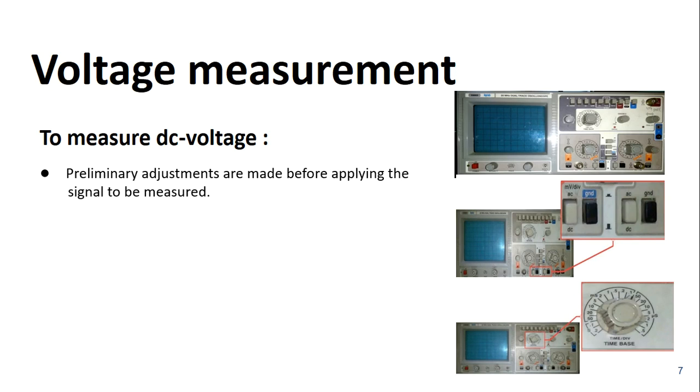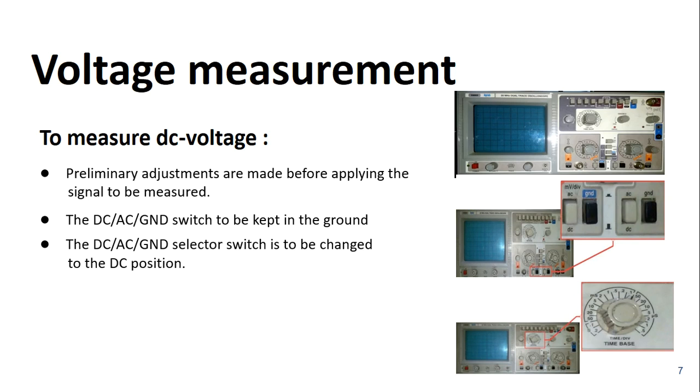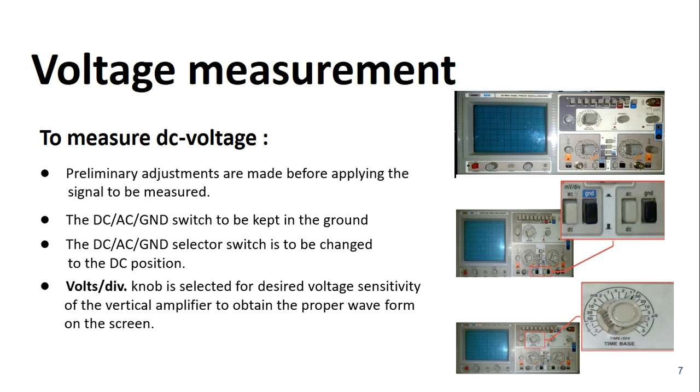Preliminary adjustments are made before applying the signal to be measured. The DC-AC ground switch to be kept in the ground, and the selector switch is to be changed to the DC position. Volts per division knob is selected for desired voltage sensitivity of the vertical amplifier to obtain the proper waveform on the screen. Horizontal controls are used to position and scale the waveform horizontally.